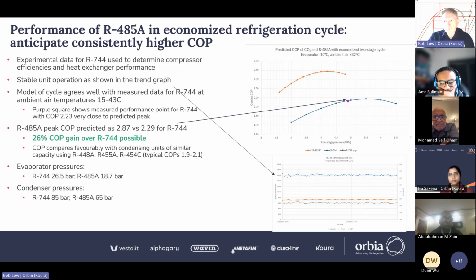So that says that we should be able to get 25% more COP for this blend in this technology. How does that compare to a fluorocarbon condensing unit? Well, I deliberately haven't shared any specific details of manufacturers' condensing units here, but having gone over a range of condensing units from a couple of the leading suppliers and looked at the COPs you might get with 448, 455, 454C blends, typically for a fluorocarbon at a -10 plus 32 rating point, you might see a COP in a condensing unit between 1.9 and 2.1, so about 2. So the CO2 system on its own is already 10% better than a typical fluorocarbon system. The catch, of course, is it's considerably more expensive as a first cost. But with the blend, we can get another 25%. So that starts to make it interesting.